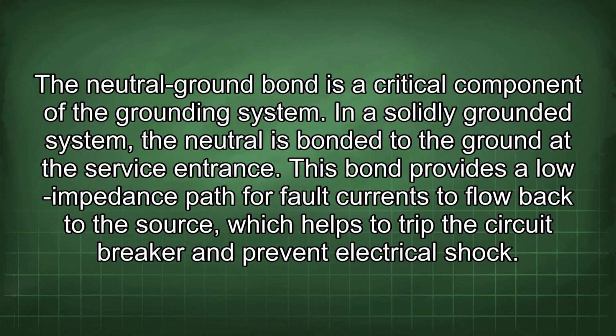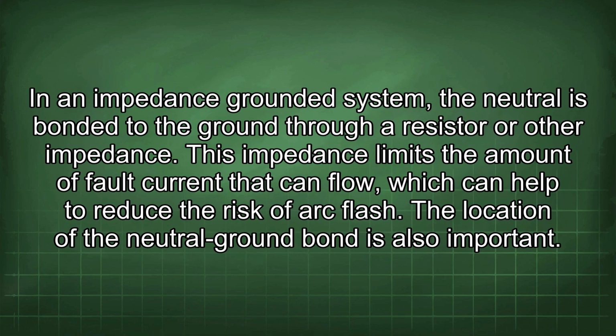The neutral ground bond is a critical component of the grounding system. In a solidly grounded system, the neutral is bonded to the ground at the service entrance. This bond provides a low impedance path for fault currents to flow back to the source, which helps to trip the circuit breaker and prevent electrical shock. In an impedance-grounded system, the neutral is bonded to the ground through a resistor or other impedance. This impedance limits the amount of fault current that can flow, which can help to reduce the risk of arc flash.